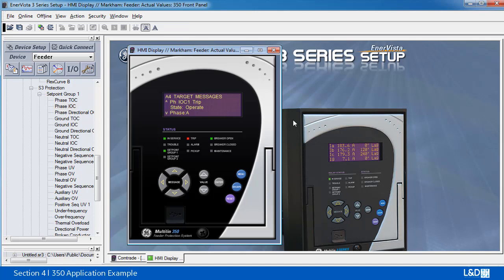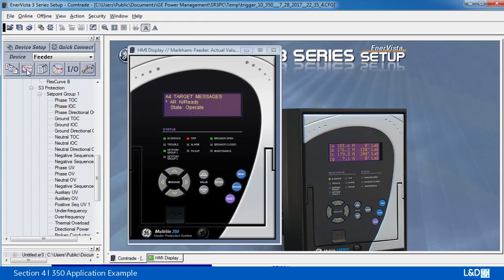I heard the relay operate multiple times. That's the trip and auto-reclose function working together. So totally it should operate 4 times. And at the end we can check the waveform by clicking this display complete record. Because this takes some time to download the waveform, I got a recorded waveform I can recall from here. So now the waveform is being downloaded from the relay.